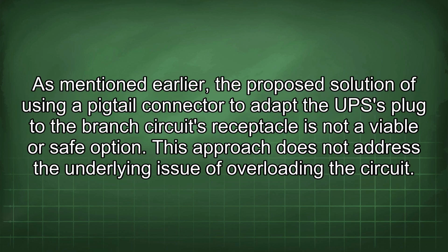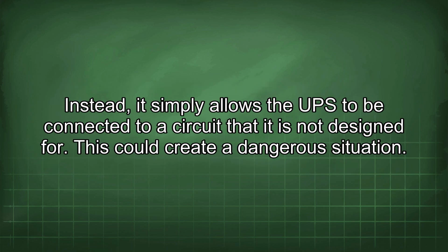As mentioned earlier, the proposed solution of using a pigtail connector to adapt the UPS plug to the branch circuit's receptacle is not a viable or safe option. This approach does not address the underlying issue of overloading the circuit. Instead, it simply allows the UPS to be connected to a circuit that it is not designed for. This could create a dangerous situation.